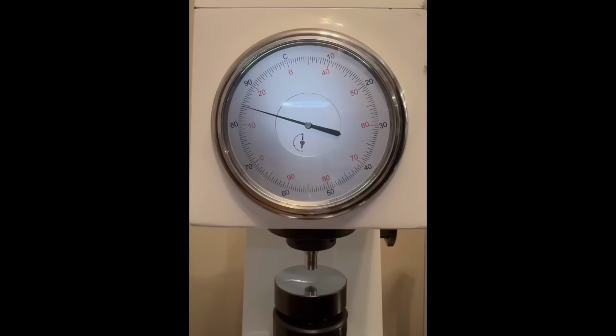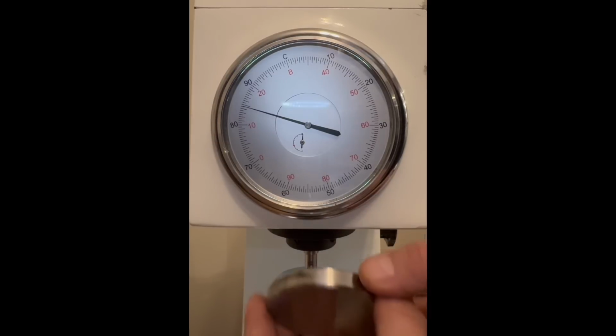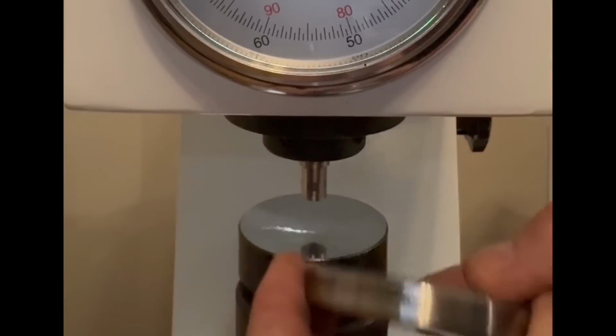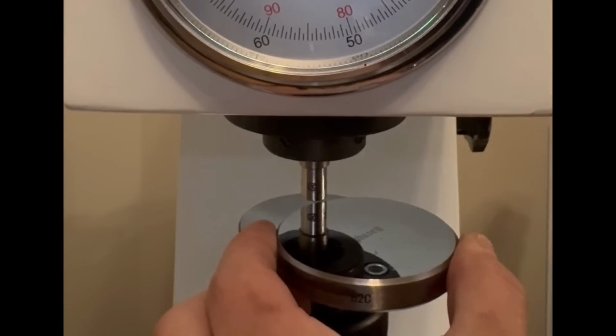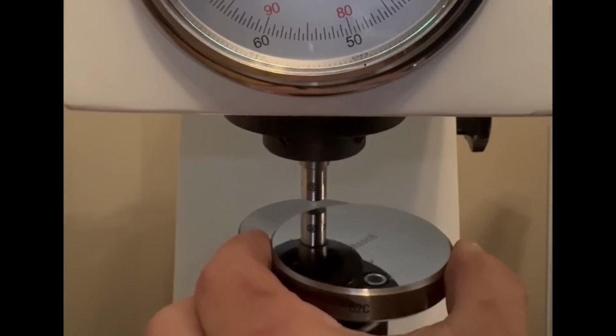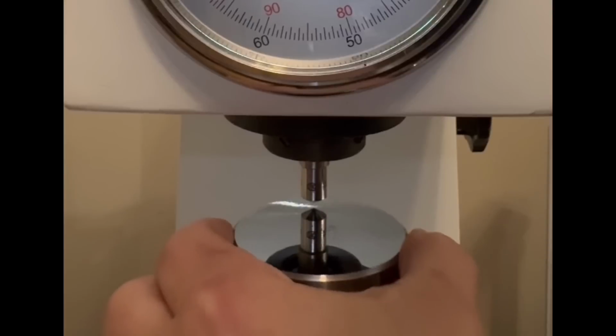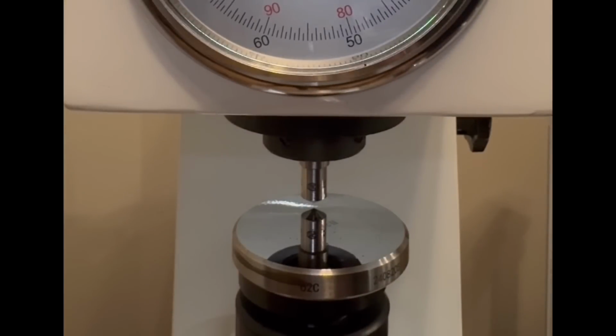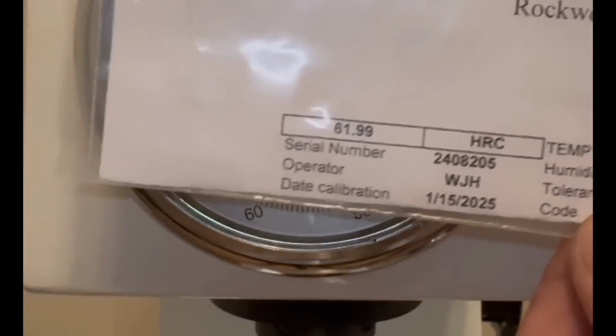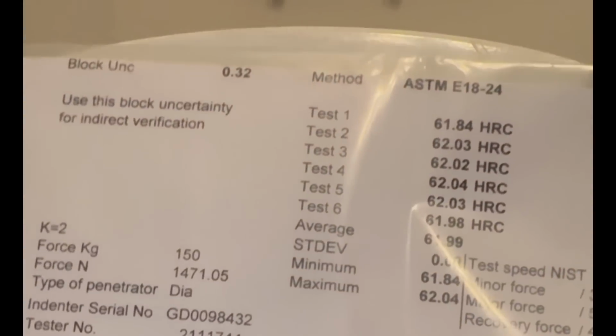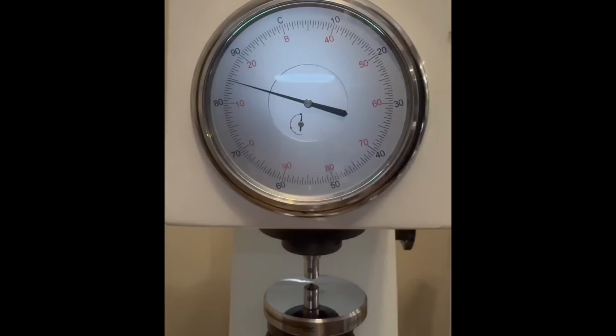I have a test block that I purchased independently from the Rockwell Tester from a very reputable company called Phase 2. And not only is it marked 62 Rockwell C from the factory, it's also serialized and is accompanied by an independent NIST compliant certificate here on your screen. You can see the serial number and all the supporting data that led to certifying this block at 61.99, or for our goals and purposes, 62 HRC.